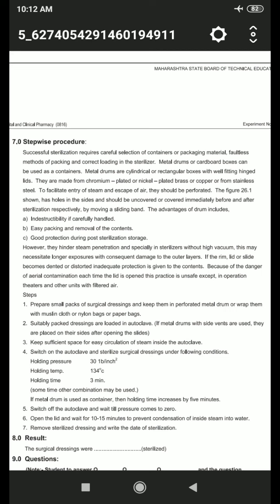However, they hinder steam penetration, especially in sterilizers without high vacuum. These may necessitate longer exposure with consequent damage to the outer layers. Then if the rim, lid or slide becomes dented or distorted, inadequate protection is given to the contents. Then because of the danger of aerial contamination each time the lid is opened, drum practice is unsafe except in operation theaters and other units with filtered air.